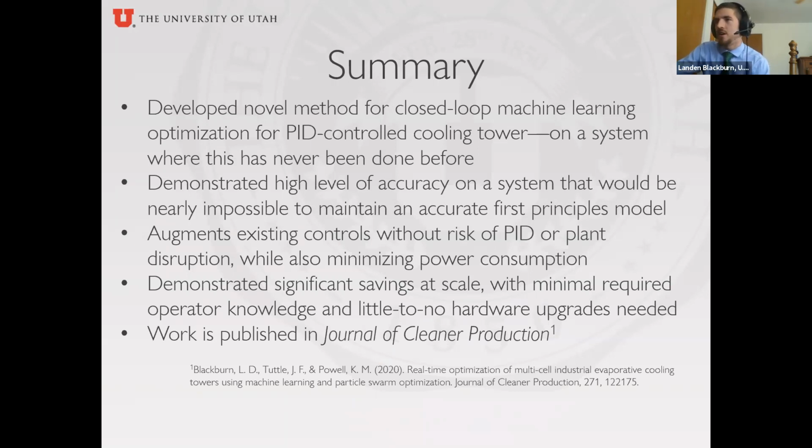So just to summarize our main contributions to this project, we successfully developed a closed loop machine learning based optimization algorithm for a cooling tower that has a PID controller. As I mentioned, one of the key design elements here was to structure it in a way that we could preserve the original control structure without having to change it a lot.